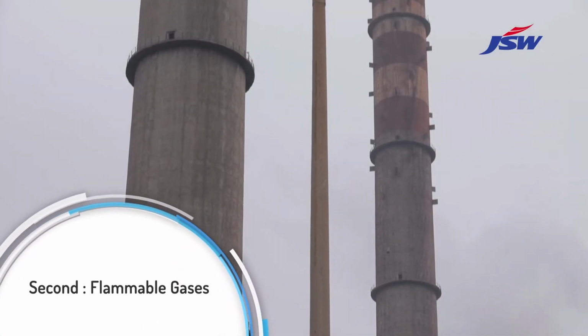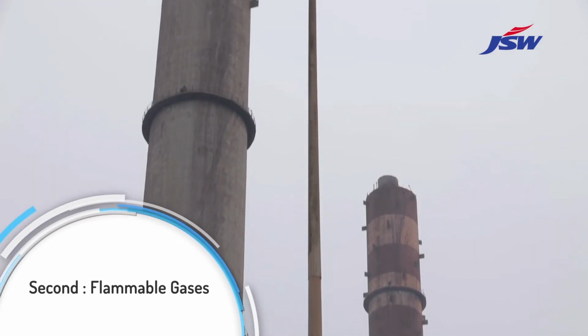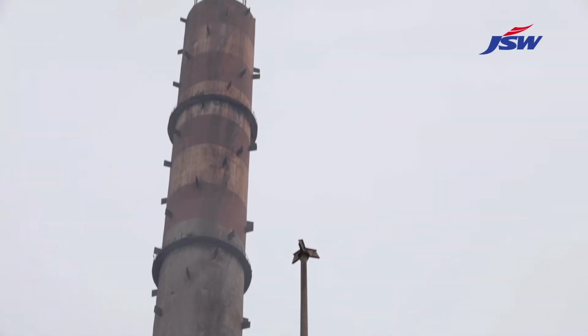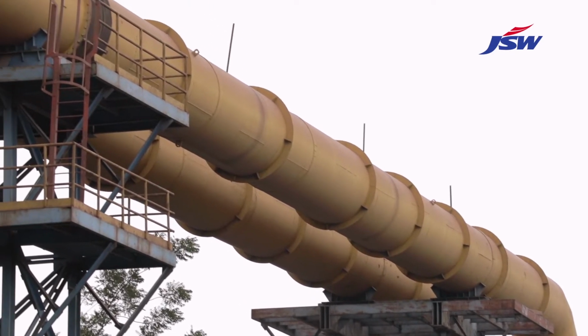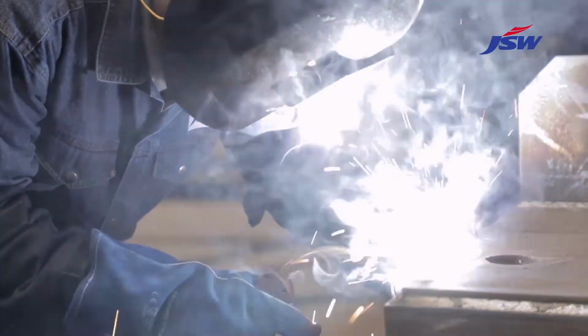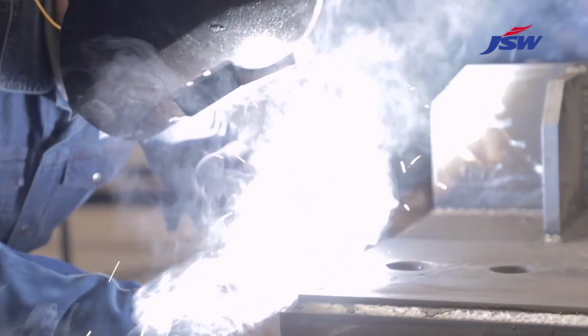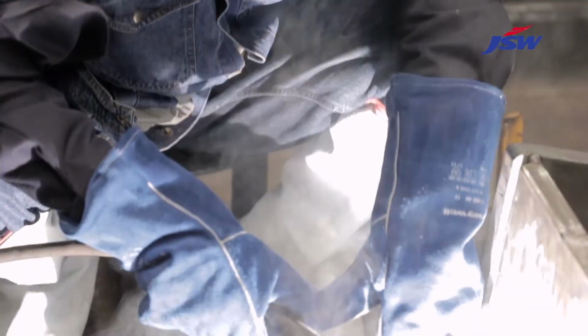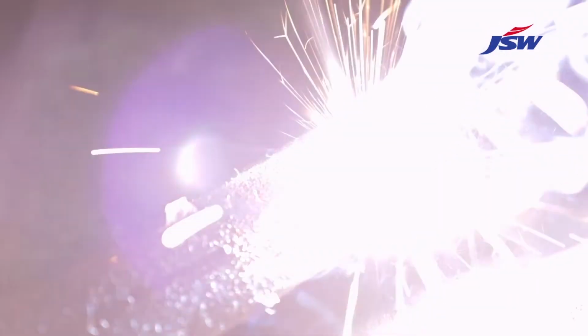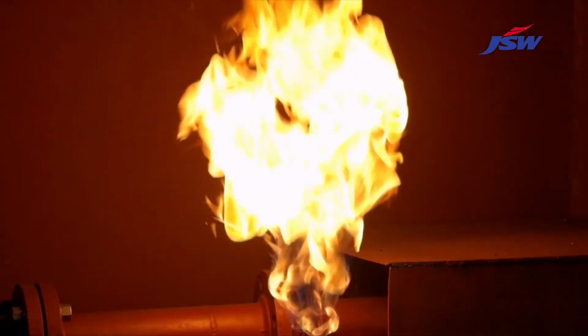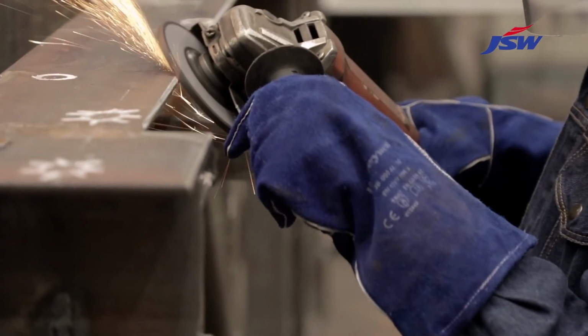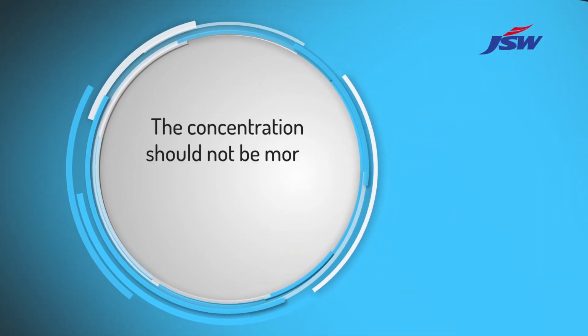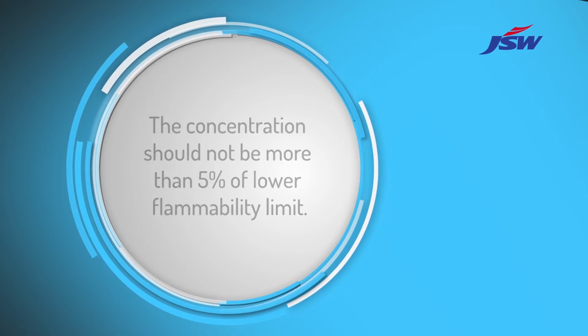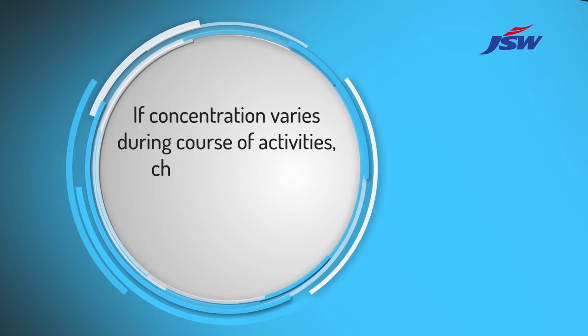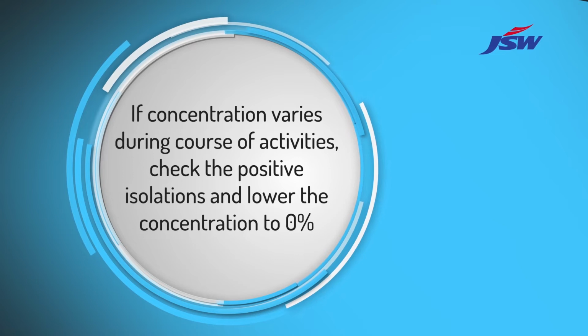Second, flammable gases through the space, covering horizontal areas as well as vertical. This is necessary because even small pockets of flammable gases in air can ignite, leading to severe damages. Flammable or combustible gases create a threat of fire or explosion. These gases are often odorless and invisible, and if the concentration of a flammable gas is high enough, even a tiny spark of static electricity can cause a catastrophic explosion. This should be below the threshold limit value. The concentration should not be more than 5% of lower flammability limit. If concentration varies during course of activities, check the positive isolations and lower the concentration to 0%.